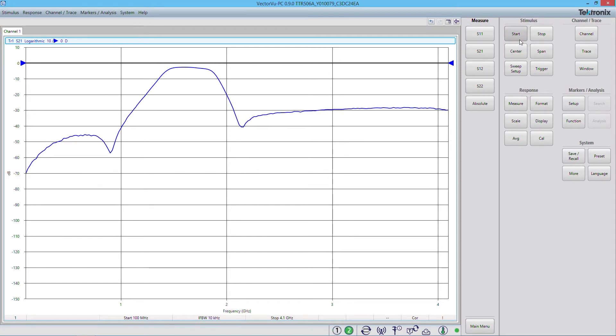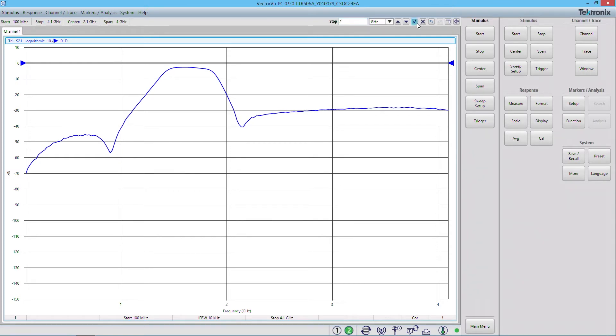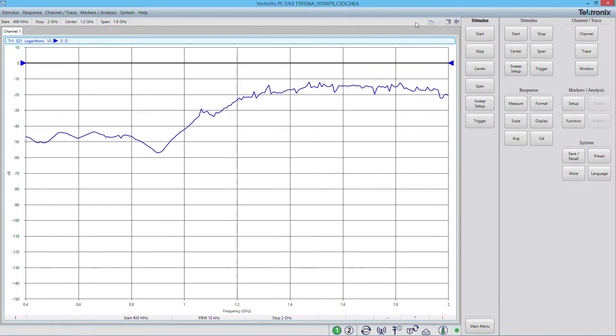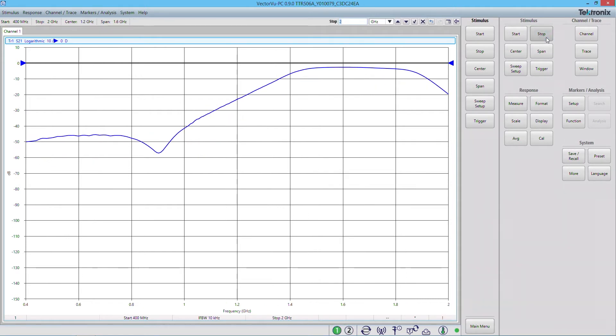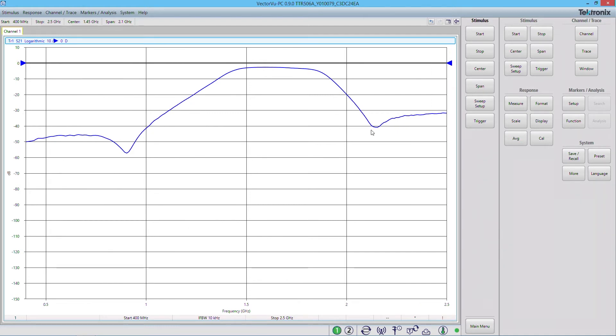And now I want to zoom in a little bit on our actual filter response here. So I'm going to adjust my start and stop frequencies. I'm going to change my stop frequency down to about 2 GHz, and I'm changing my start frequency all the way up to about 400 MHz. I have a slightly clearer picture. I'm actually just going to move the stop frequency out a little bit more to about 2.5 GHz. It's going to be a very good picture of our filter response.